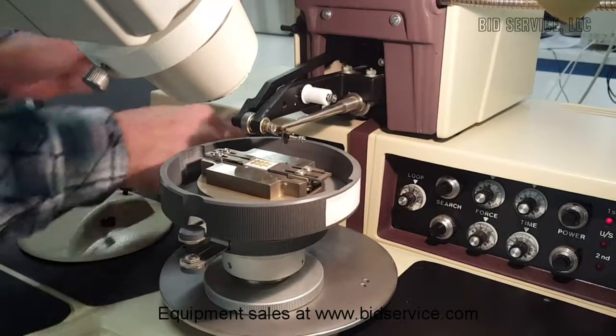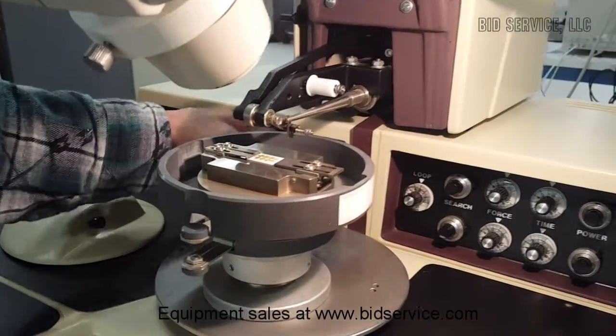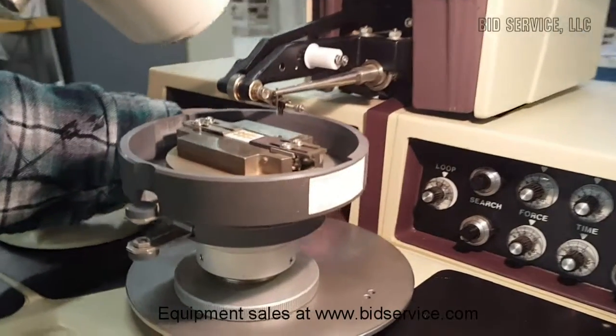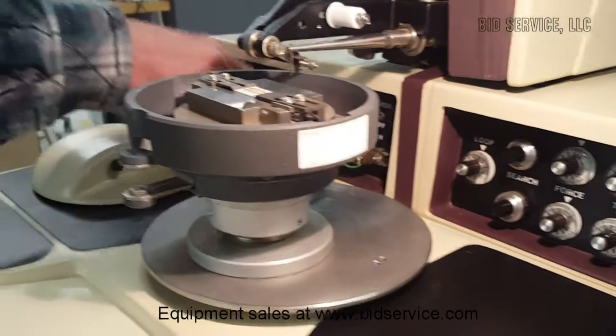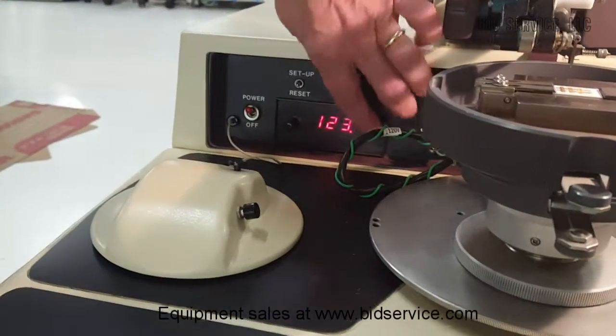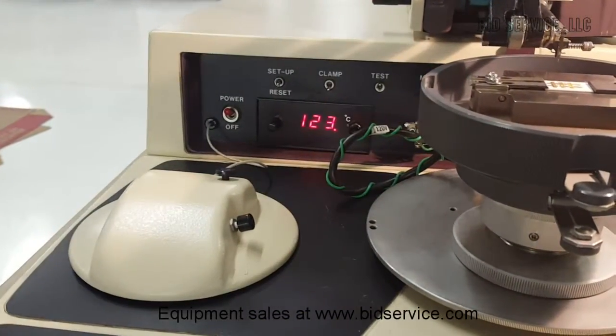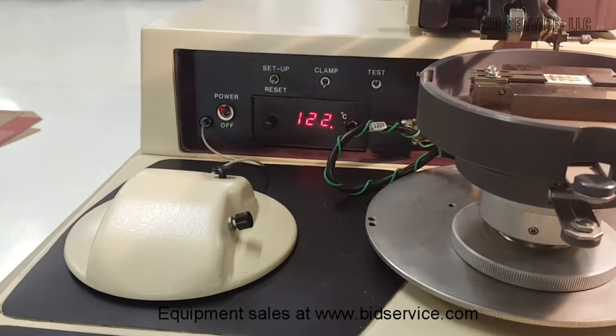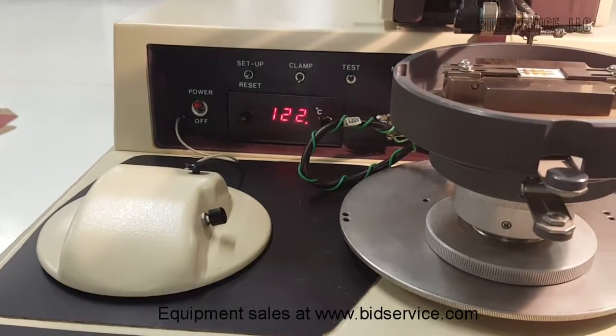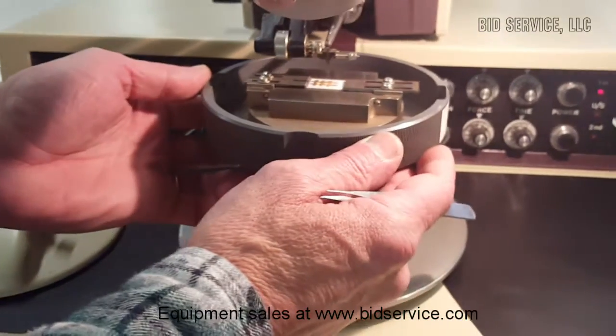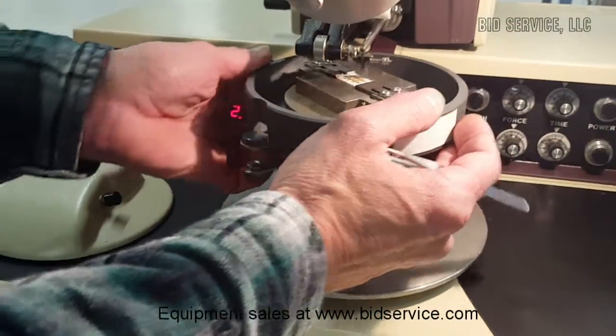This is a heated work stage. The connector for the heated work stage is right here, and here's your temperature controller. It's recommended that you set it to 150 for gold wire bonding. Aluminum, you don't need heat. Again, this is the house work holder, so this will not be supplied with your system.